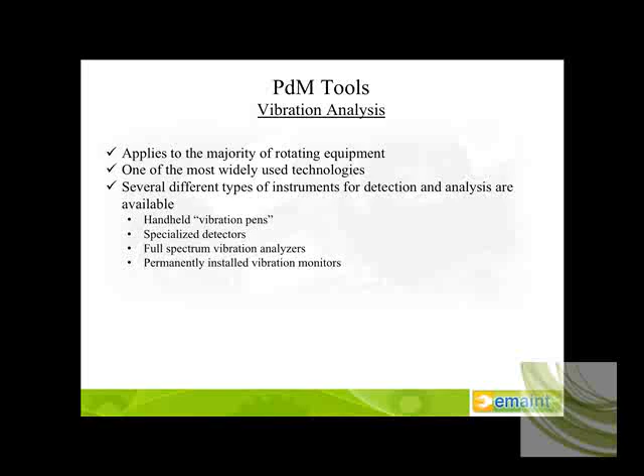Now, on the full spectrum analyzers, typically what you might see a service provider use or look at for in-house programs. Some of the pros, they're a little bit more sensitive, so they have the capability of maybe detecting nearly all machine faults as compared to the sensitivity of a vibration pen. Multi-channel measurement capability, extremely powerful software for trending and analysis. With the full spectrum analyzer, you also have balancing capability, built-in route management, and bearing measurement data is at times included in those multi-spectrum analyzers. However, one of the largest cons is a relatively high cost of purchase for the full spectrum analyzers.